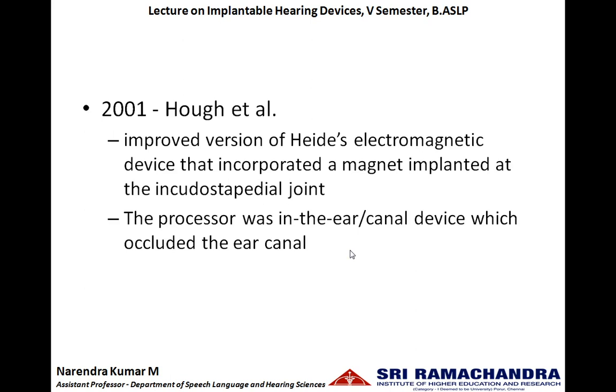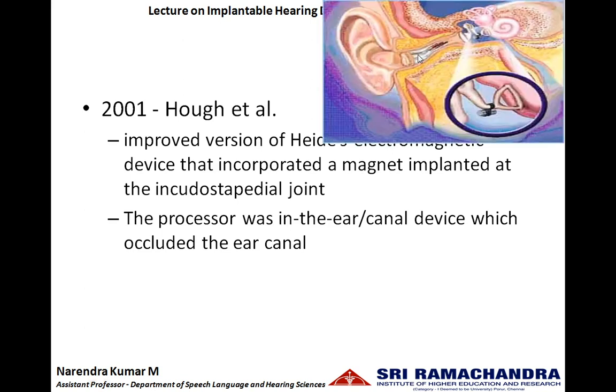In the year 2001, Hough et al. improved the version of Heide's electromagnetic device. Here, the transducer incorporated a magnet implanted at the incudo-stapedial joint, whereas the processor was either an in-the-ear or in-the-canal device, which would occlude the ear canal. So the in-the-canal hearing aid has the microphone, amplifier, and the induction coil as the external device, and the internal device is a magnet placed on the incudo-stapedial joint. Depending upon the incoming sound, magnetic waves are generated by the induction coil, making the magnet to vibrate.